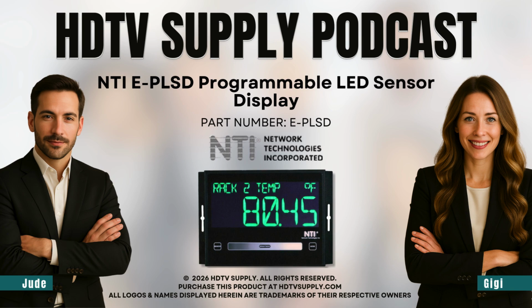Let's talk installation for a second. It uses RS-485 communication, so you connect it with standard Cat5 or Cat6 cable. How far away can you put this thing? Up to 1,000 feet away from the main EnviroMux unit. That's a pretty good distance. It is, but here's the really smart piece of engineering I found in the specs.